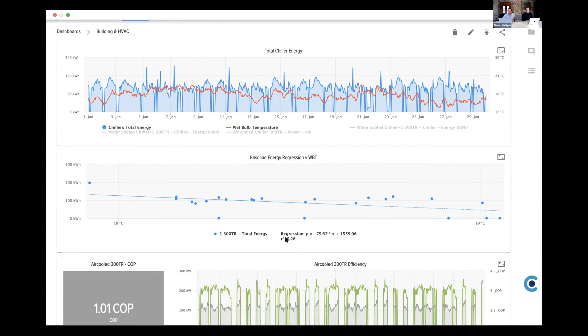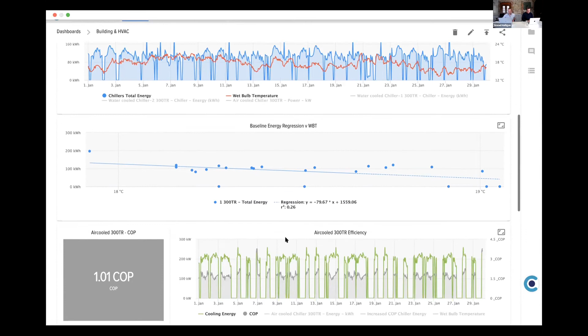For those of you that understand linear regression, you're looking for a high R² value - anywhere between 0.8, you're never going to achieve 1, but between 0.8 and 0.99. In this case it was 0.26, so no correlation - these two variables are not impacting one off the other at all. So straight away he was thinking there's either no control on this system or very little control.